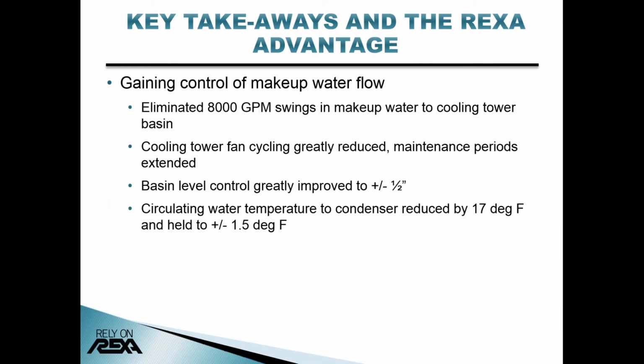Buddy, with your experience at the plant and having lived through improvements, would you like to comment on this bullet and the next few? Sure. By improving the temperature delta in the cooling tower and the circ water basin, we've been able to optimize even the cooling tower performance, where before we were running at a higher temperature to stabilize other plant processes that were coming off of the main circ water system. We were able to lower the entire circ water system and still maintain adequate control within the facility.